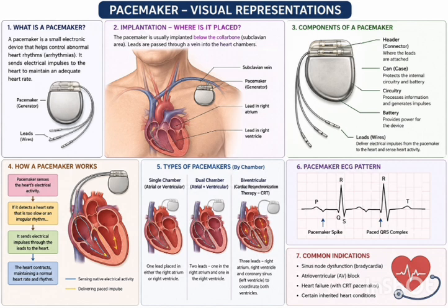So the principle of the pacemaker is that the pacemaker works on the principle of electrical stimulation. Based on this principle, it continuously monitors the heart's electrical activity. Whenever it detects that the heart rate falls below the programmed limit or no heartbeat is present, it delivers a small electrical pulse through the leads to the heart muscle. This electrical pulse causes the myocardium to contract and produce a heartbeat.